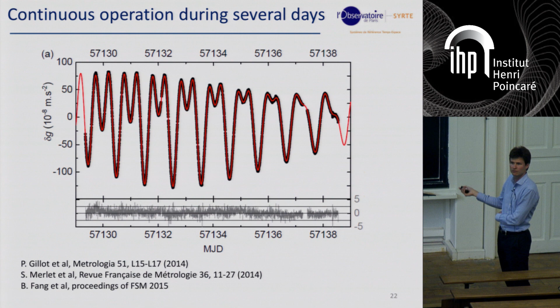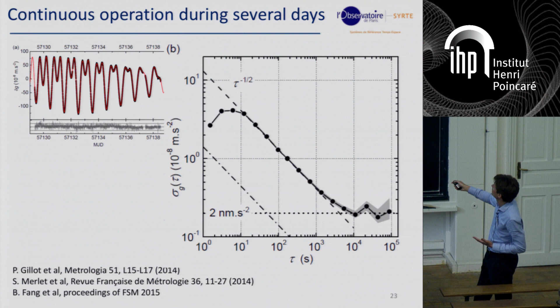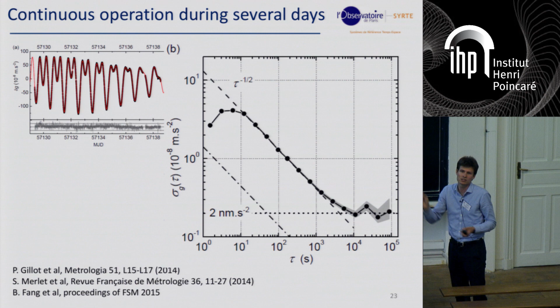This is a statistical tool I introduced. When we look at the stability of a sensor, we look at how the noise averages down when you increase the measurement time. What you remember from the practical course is that if you do n measurements, and if you do it rather well, the error decreases by square root of n if the measurements are uncorrelated. This is expressed as a so-called Allan deviation, which is basically the RMS noise as a function of time. If it goes well, it goes as 1 over square root of time. After typically 3 hours of measurements, so 10⁴ seconds, the uncertainty is on the order of 10⁻¹⁰ g. So you can resolve after 3 hours changes of 10⁻¹⁰ g. In fact, you can do a bit better now.